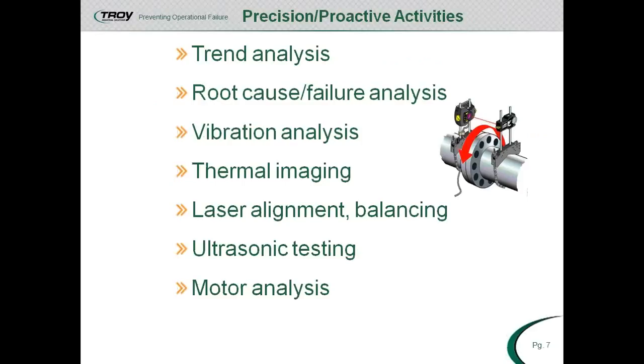So, the precision proactive activities. What are the methods that we use to get to where we want to be? We spoke earlier of trend analysis. All of these instrumentation devices that we utilize have the ability to take data and measure the current situation under certain load conditions, and it records it. If we log all this data and record it over time, and we make a particular note in this trend data, we'll take all of this data over time and create lines and graphs. We can look at root cause and failure analysis, and we can take all this information together and arrive at conclusions that either it's in good shape or it's in bad.